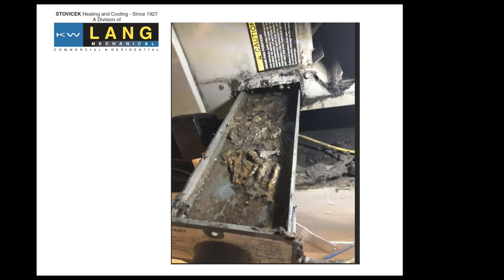This is an evaporator pan that collects the condensation off the evaporator. Typically when we come in and do maintenance, we flush the pans out and clear the drains — that's in the spring or early summer. You're making condensate all summer long, and it can get really slimy. This one hadn't been looked at in a couple of years, and you can see it has some growth going on and is pretty slimy. Some applications, we put what's called pan tablets or pan socks in there, which actually prevent mold and slime and also prevent the drains from getting clogged and causing leaks.